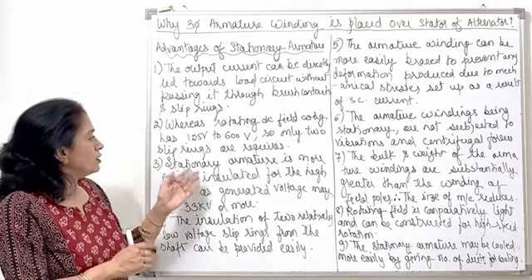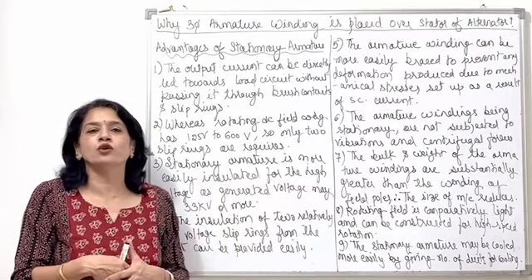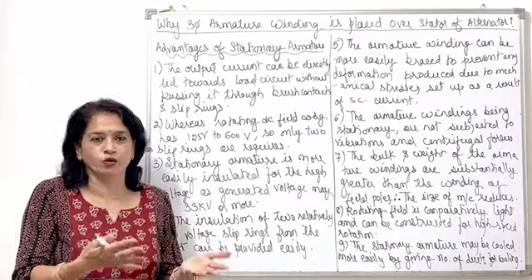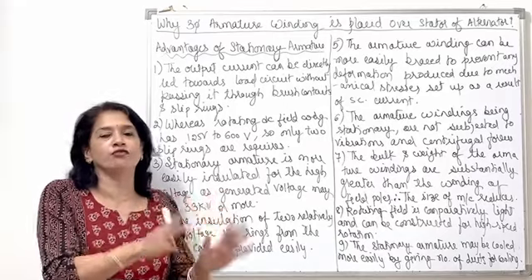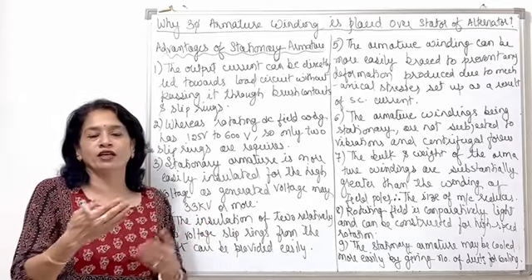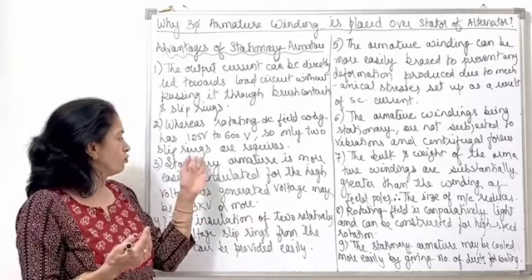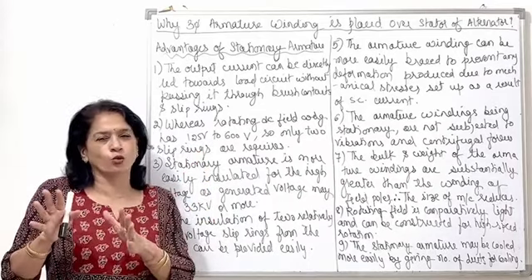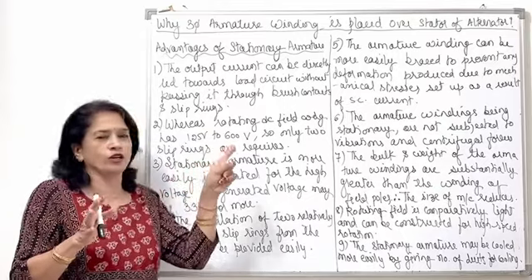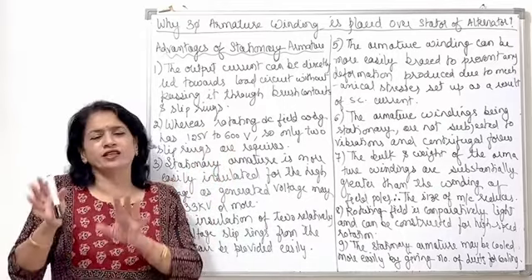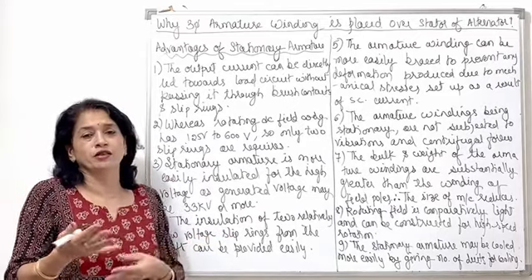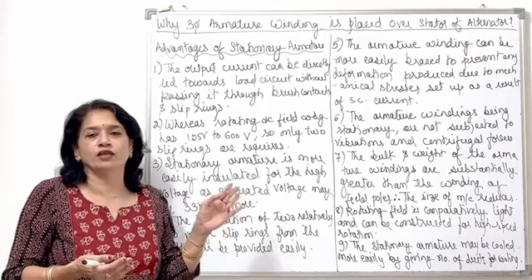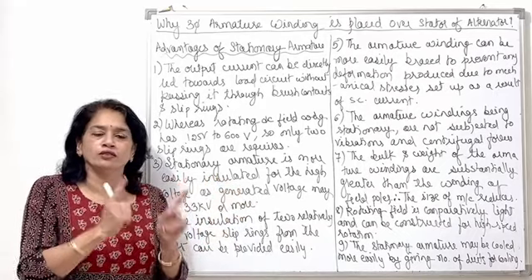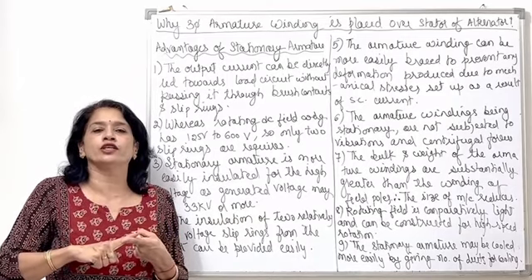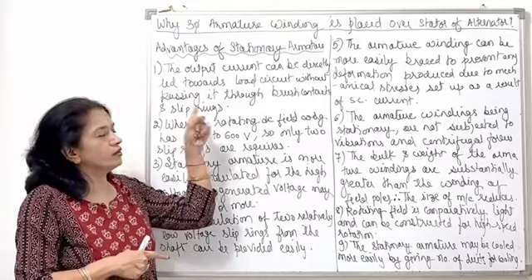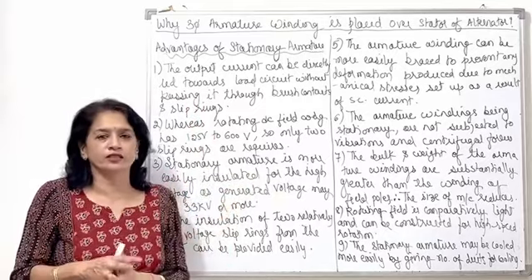So it is always better to have the three-phase armature winding, inducing high voltage, provided over the stator. Next, the stationary armature can be easily insulated against the high voltage, because it is quite easy to maintain the insulation of a high voltage winding if it is stationary. Similarly, the insulation of the rotating DC field winding having a voltage of 125 to 600 volts is quite easy to handle. So it is preferred that the three-phase armature winding inducing high voltage be provided over the stationary stator, so that we can maintain high voltage insulation and the connection with the load circuit without slip rings and brushes.